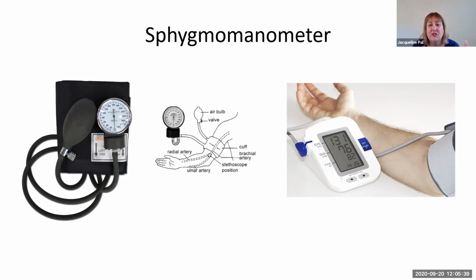Okay. And so the traditional sphygmomanometers are the ones that you see on the left where there is a dial. We're not using the mercury on the wall anymore. We have changed that to talk about air calibration to this dial. And the dial is kept over the blood pressure cuff area, so it's in the right part of the body. And then you have a little squeeze bulb and a little dial so that you can close it to prevent air from coming out, or open it slightly so air comes out slowly. So after you have pumped it up, all of a sudden the air isn't whooshing out, but it's coming out slowly, so you actually can listen for the sounds of the blood flow in the artery.